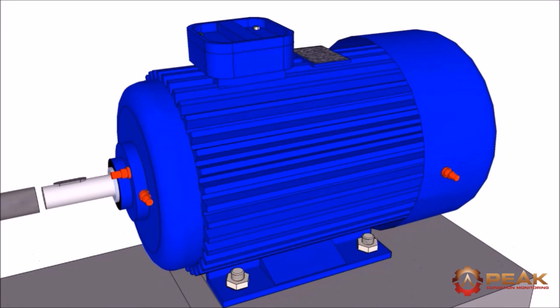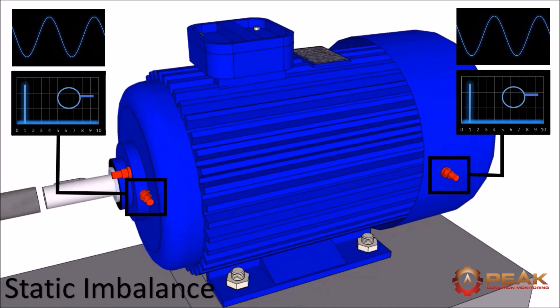Let's assume the fault's present in the motor. A high 1x peak could indicate one of three types of imbalance. The only way to differentiate between them is by measuring the phase of the vibration.